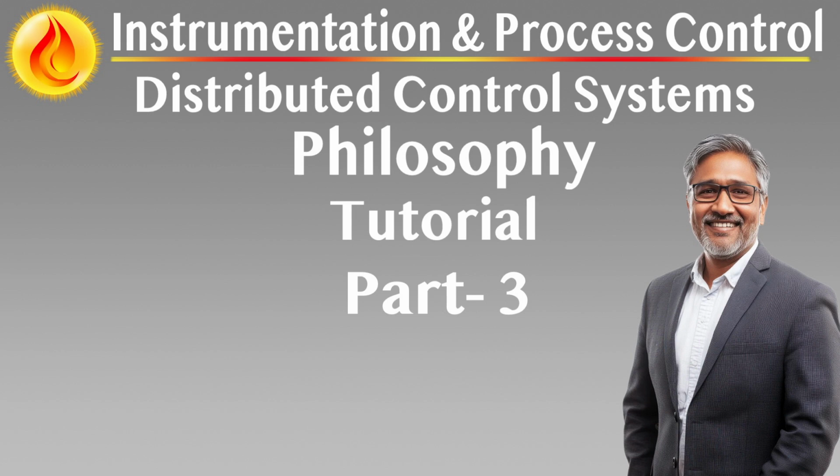System output design and response strategy. Default to de-energize to trip philosophy. All field outputs are fail-safe, de-energized to activate safety action. Actuators, e.g. dampers, solenoids, revert to their safe position on loss of signal, power, or FGS system integrity.